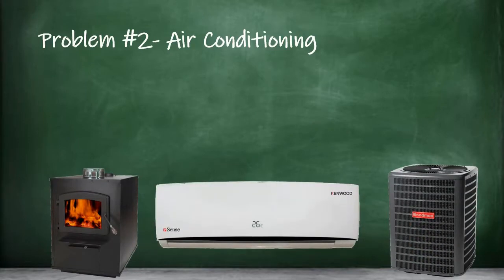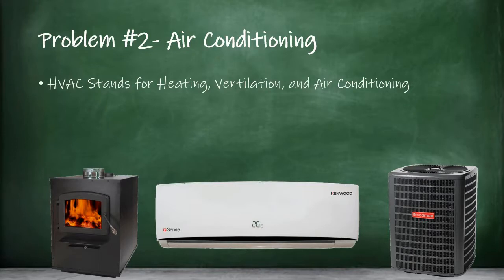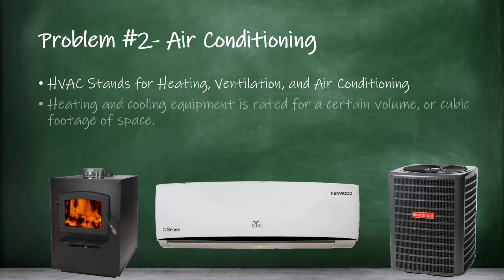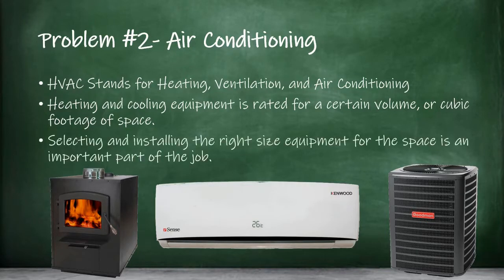One reason that a homeowner, contractor, or designer might need to calculate the volume of a space is when they're trying to install HVAC equipment. HVAC stands for Heating, Ventilation, and Air Conditioning. If an HVAC technician is installing a furnace or an air conditioner in a home, they need to understand the volume of the space being heated or cooled in order to choose the right one. Too big and the system will cost too much and might overpower the space, making it too hot or too cold. Too small and the system might not be able to heat or cool the space properly, leading to high energy bills and premature wear on the system. To figure out the right furnace or AC for a space, the volume of the space needs to be calculated.